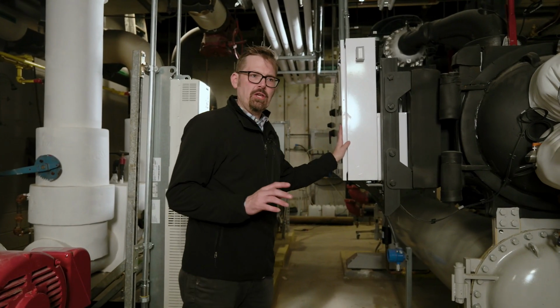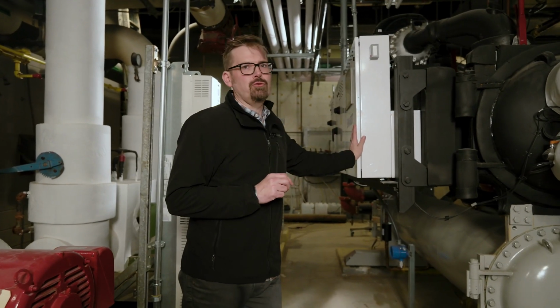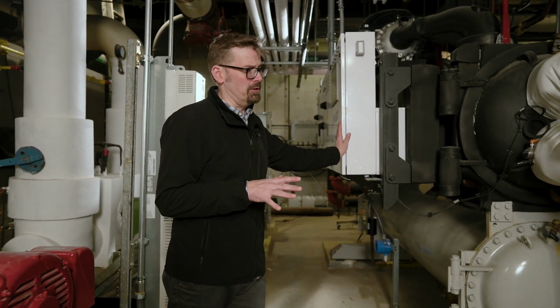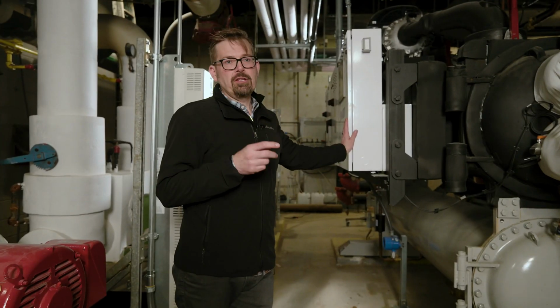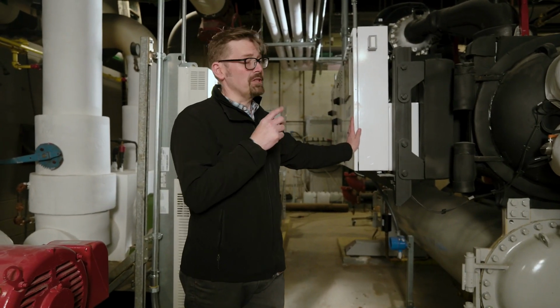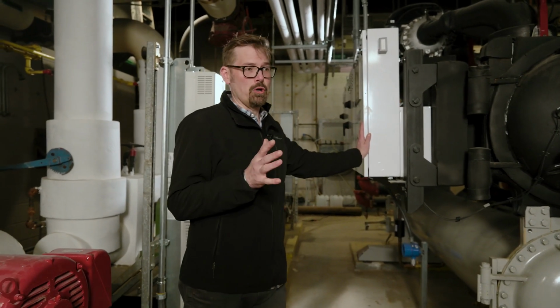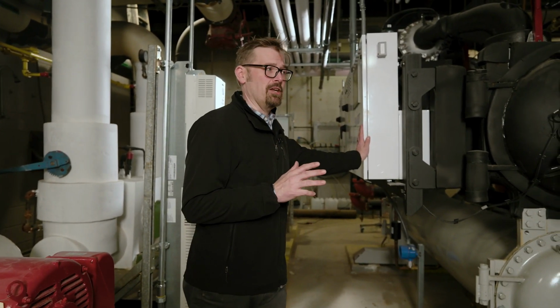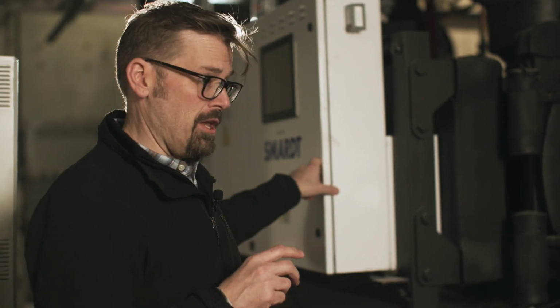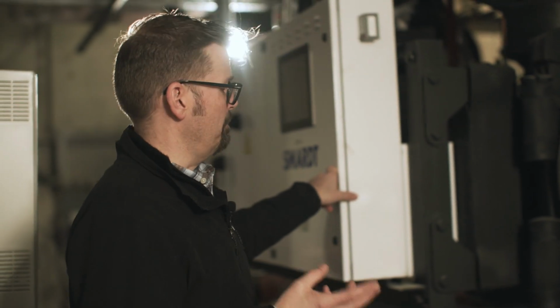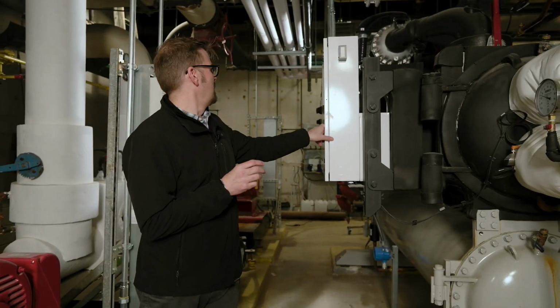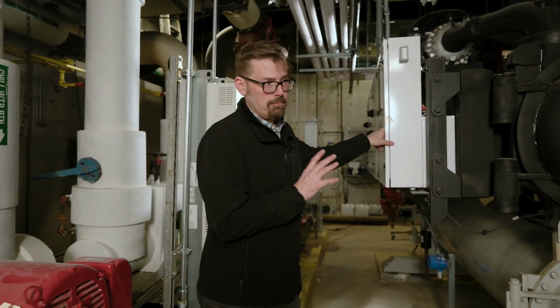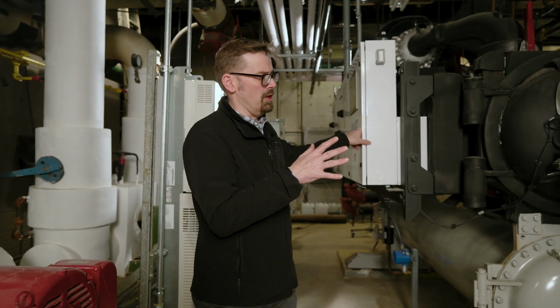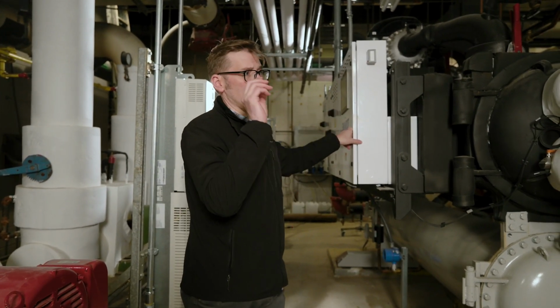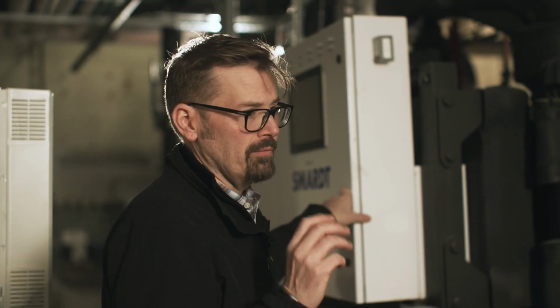About a year and a half ago, we replaced 2 old 1972 Trane chillers that were existing in the building. One was decommissioned and another one was, I guess you'd call it, a Frankenstein chiller. They had taken Turbocor cores and added them to a Trane barrel. It worked, but we were past the capacity of that chiller. So to bring the building back up to an energy efficient and working chiller plant, we went with the Smardt chiller packages. So you have 2 chillers of the same tonnage here. Both of these chillers supply the house air system with their cooling.